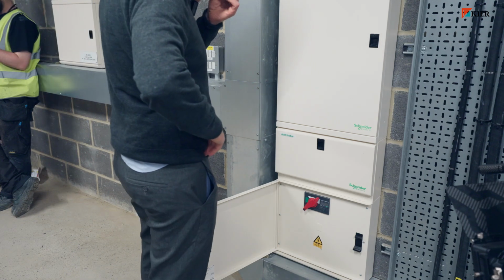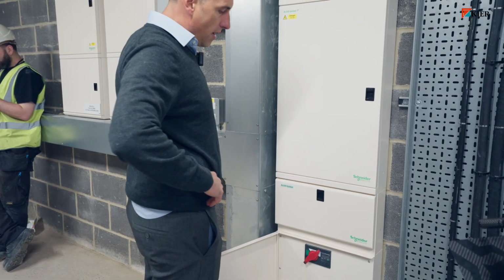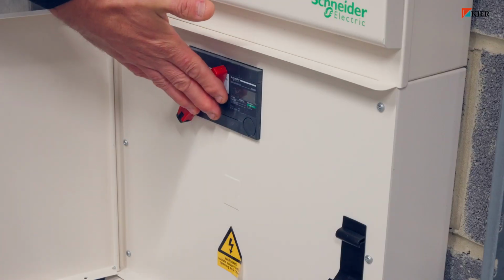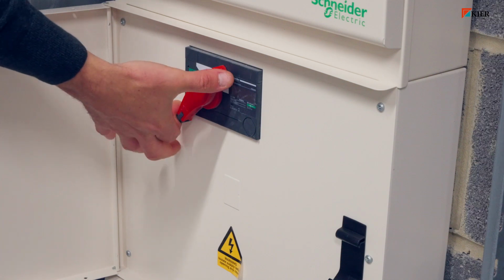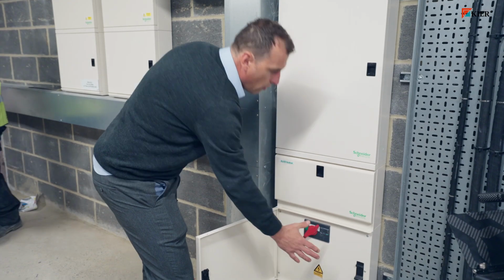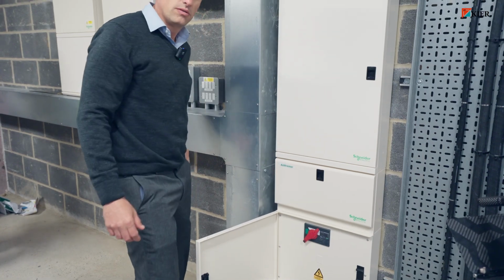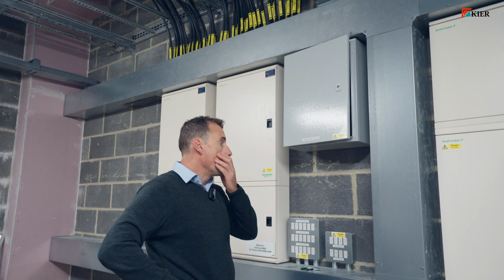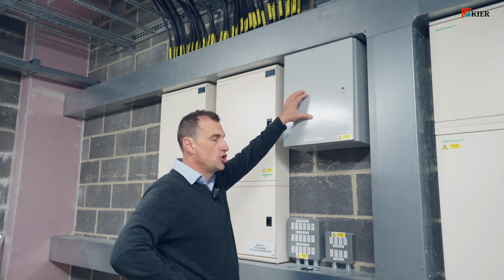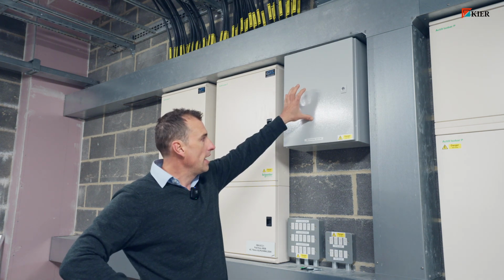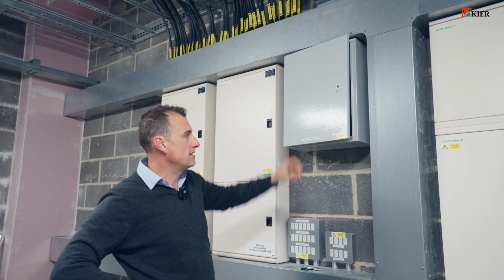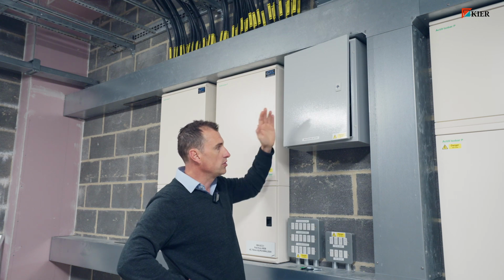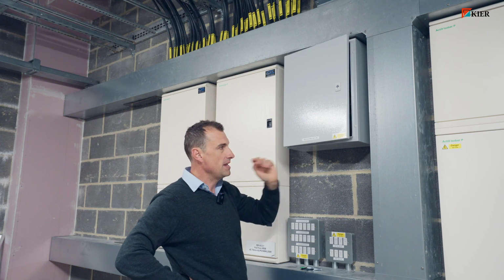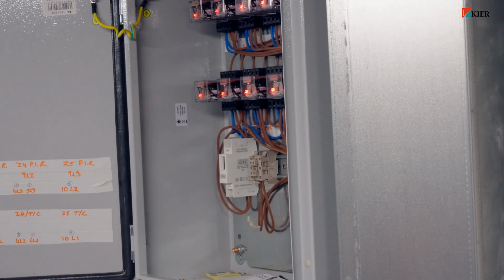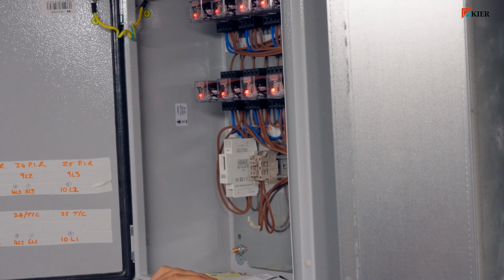In the event of wanting to isolate the power and lighting boards combined, all boards are fitted with an isolator. The same principle applies. Just rotate the switch from the on position to the off position, and that will then de-energize both lighting and power boards. On each of the floors, we have an enclosure which houses the time clock and some of the lighting controls. We have preset all settings on the internal floors to come on at 6 a.m. and switch off at 10 p.m. in the evening, and this houses the time clock. This should not need to be set up at all.